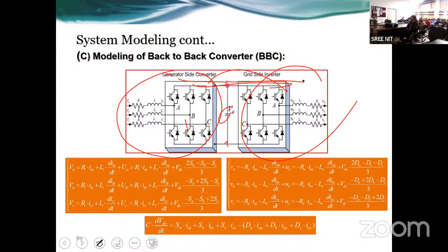So that's why maintaining the DC link voltage constant is essential. Once your DC link voltage is maintained, that means under variable power generation, the power is being transferred directly to the grid because the capacitor voltage is maintained. If the capacitor voltage is fluctuating, that means your regulator is not working perfectly, and whatever power you are generating is either absorbed by the capacitor or raising the voltage of the capacitor. So it is not going perfectly to the grid side.